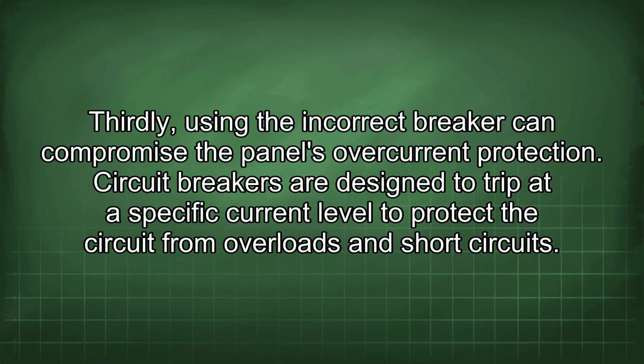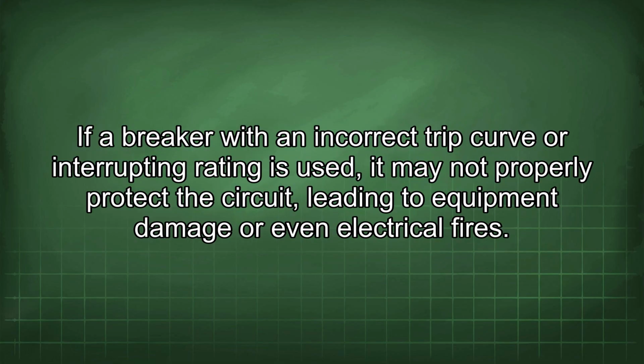Incompatible breakers may not make proper contact with the panel's bus bars, leading to overheating, arcing, and potential fire hazards. Using the incorrect breaker can also compromise the panel's overcurrent protection. Circuit breakers are designed to trip at a specific current level to protect the circuit from overloads and short circuits. If a breaker with an incorrect trip curve or interrupting rating is used, it may not properly protect the circuit, leading to equipment damage or even electrical fires.